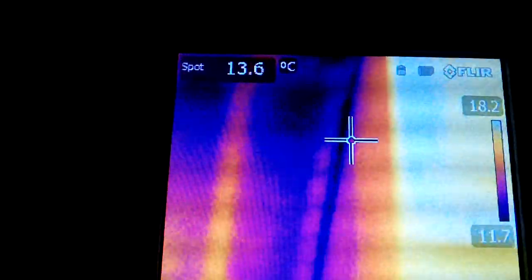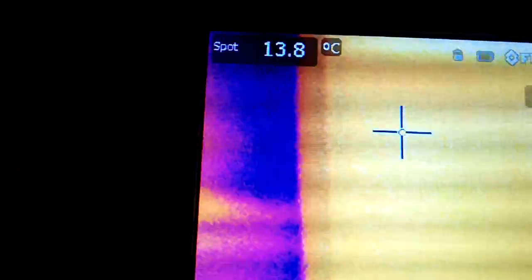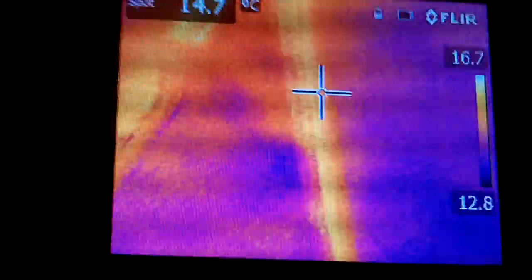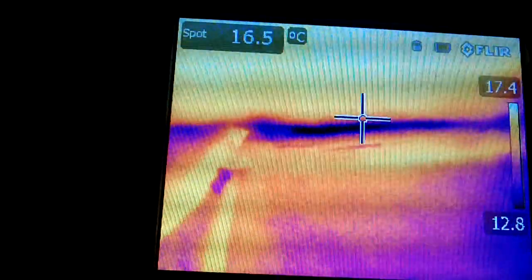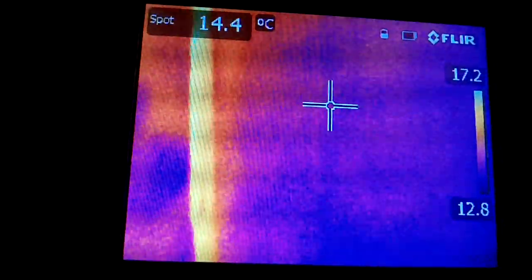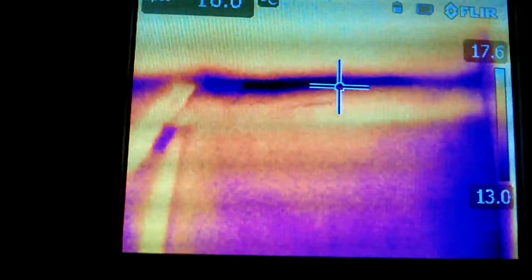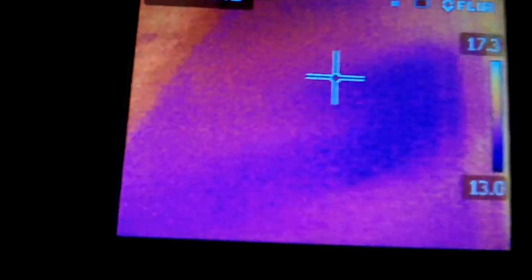So that's why we're losing heat in this house. That's an external wall that goes through to the outside gable. And interestingly, you can see that that's actually relatively warm compared to some parts of it. And that is because that particular wall — you can see it's got a linear structure to it — and there is actually part of the wattle and daub in there. And the wattle and daub is quite warm.